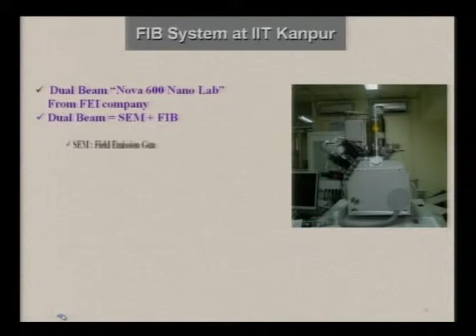Energy is 500 electron volt to 30 kilo electron volt. Current is 0.7 pico ampere to 37 nano ampere. Beam spot size is 1.1 nanometer at the optimum conditions, and magnification is as high as 6 lakh times. You can obtain the magnification. Focused ion beam, gallium liquid metal ion source. In this particular case, energy and current are as mentioned over here, and beam size is 7 nanometer at optimized conditions.